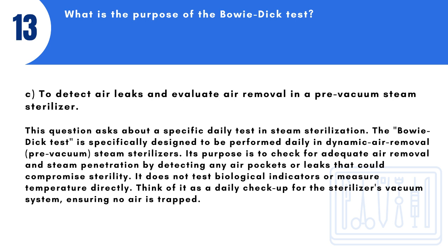It does not test biological indicators or measure temperature directly. Think of it as a daily checkup for the sterilizer's vacuum system, ensuring no air is trapped.